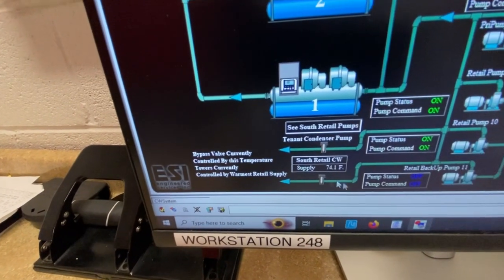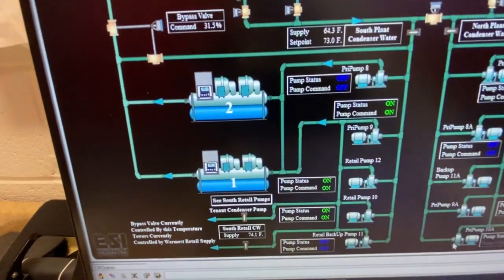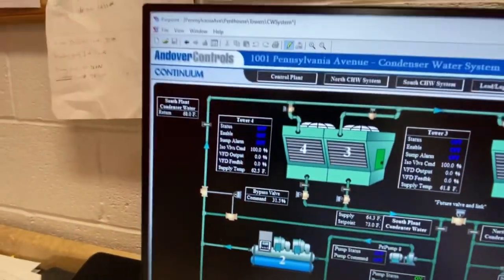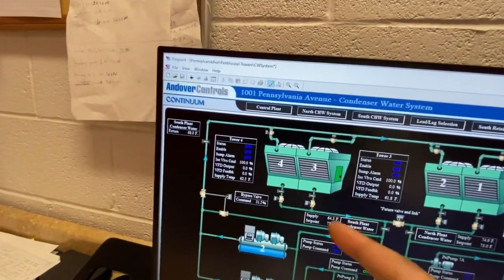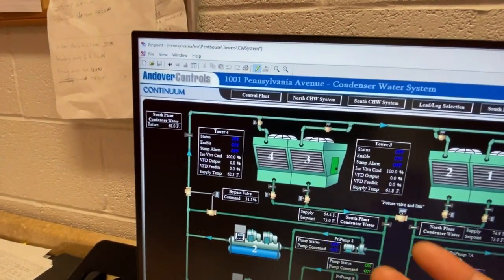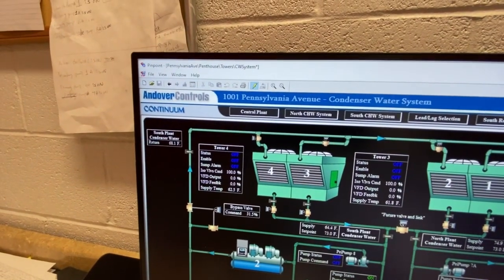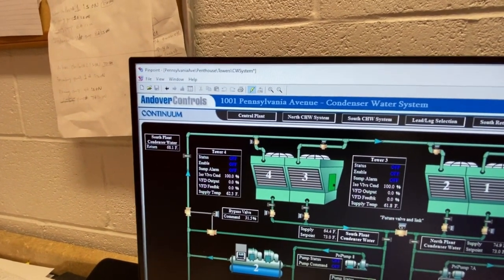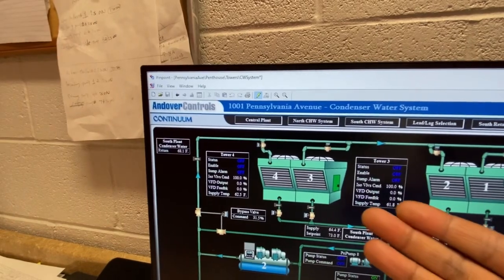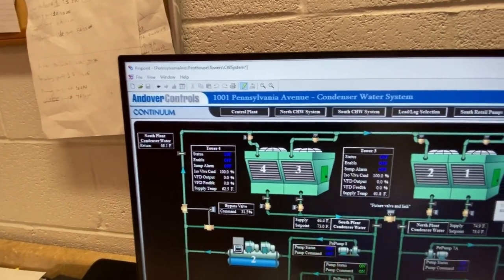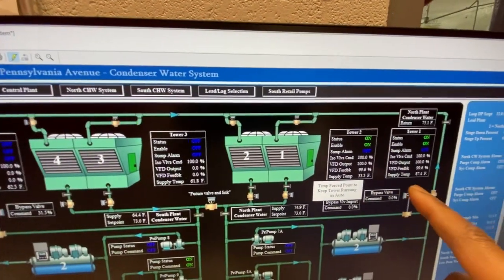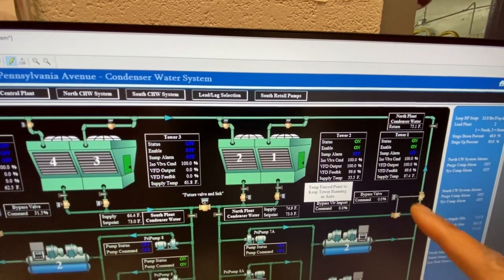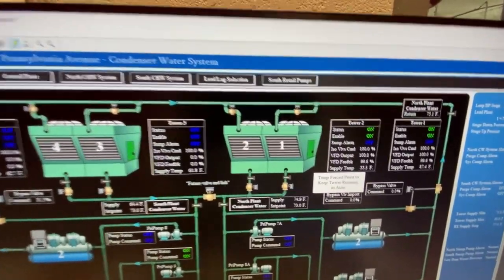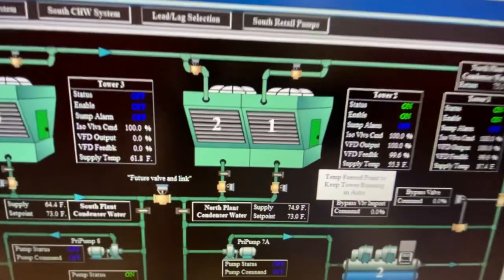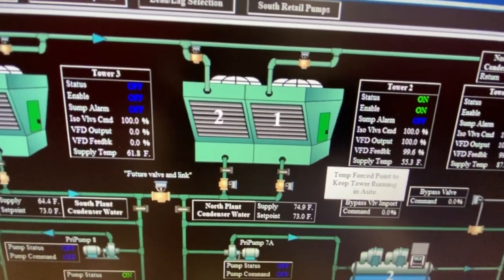Supply is 74.1. These two sets of towers, 4 and 3, are off right now, but it's automatic. They're on a VFD, a variable frequency drive. So right now it's not demanding for the towers to be on. That's the reason why they're off. But as you can see on the other side, north plant, we have towers 2 and 1 on right now. The VFD is at 99.6%, so it's almost at 100%.